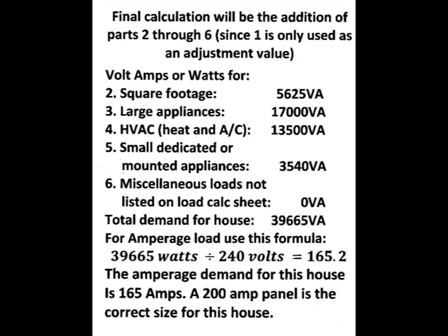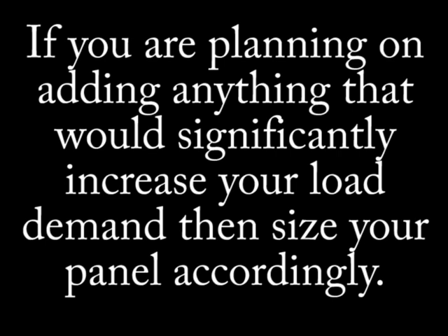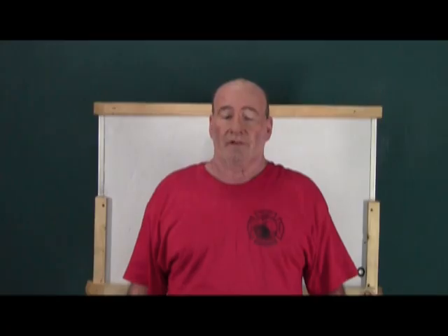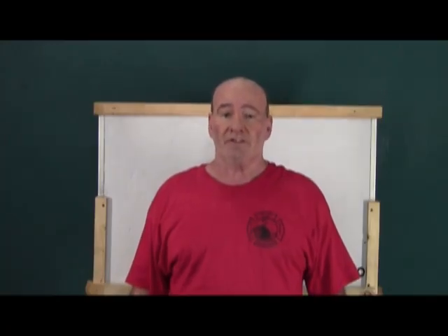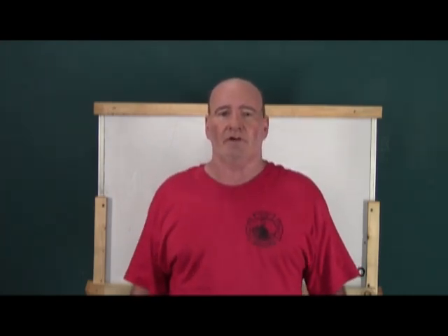For amperage load, use this formula: 39,665 watts divided by 240 volts — that gives you 165.2 amps. The amperage demand for this house is 165 amps. I would recommend a 200 amp panel for the correct size of this house. That basically is how you fill out a load calculation application. That just about wraps up this episode — thanks for watching and have a great day.